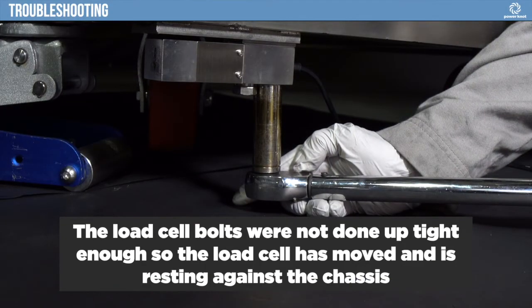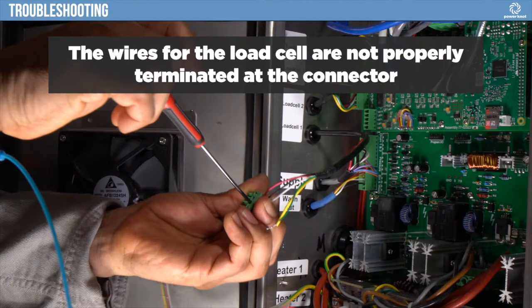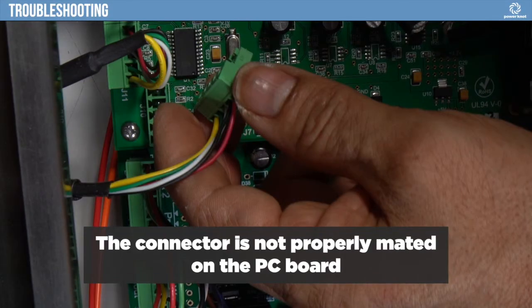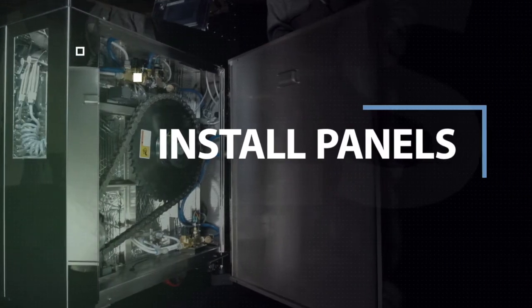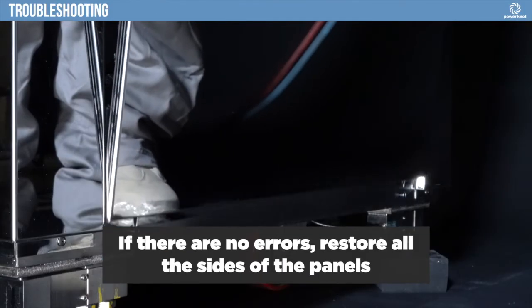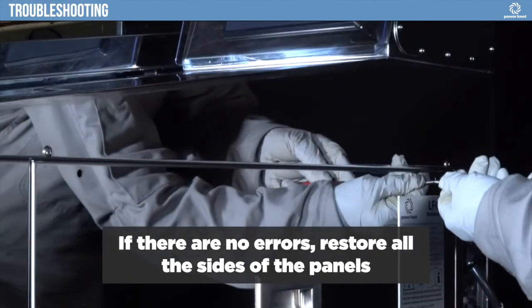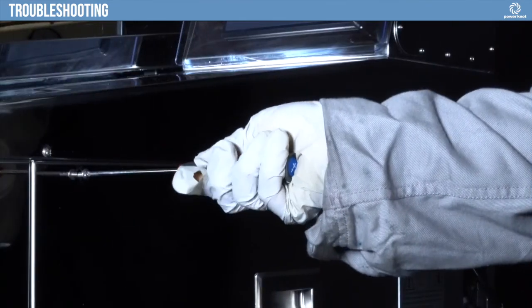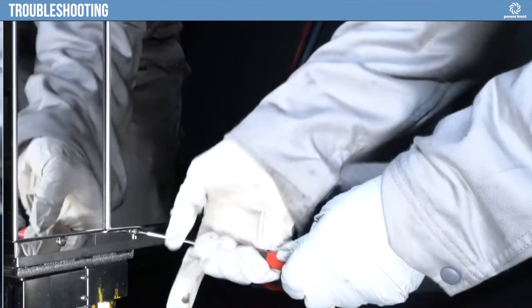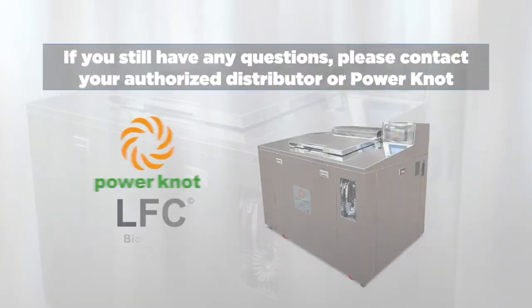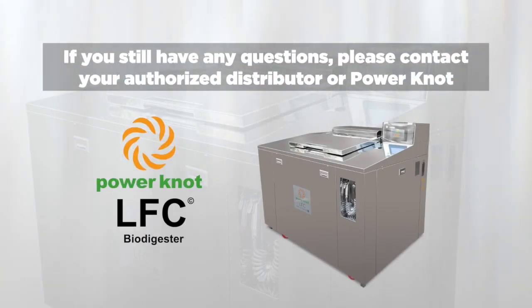The load cell bolts were not done up tight enough, so the load cell has moved and is resting against the chassis. The wires for the load cell are not properly terminated at the connector. The connector is not properly mated on the PC board. If there are no errors, restore all the side panels. If you still have any questions, please contact your authorized distributor or Power Knot.